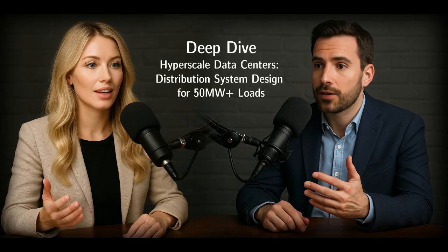One more power quality issue, flicker. Where does that typically come from with data centers, and what are the solutions? Flicker, those rapid voltage fluctuations that can make lights visibly dim and brighten, can come from a few sources in data centers. Big culprits include the switching operations of their uninterruptible power supply, UPS systems, especially during bypass or testing. Also, synchronizing on-site generators, starting large motors for cooling systems, and even utility capacitor bank switching can contribute.